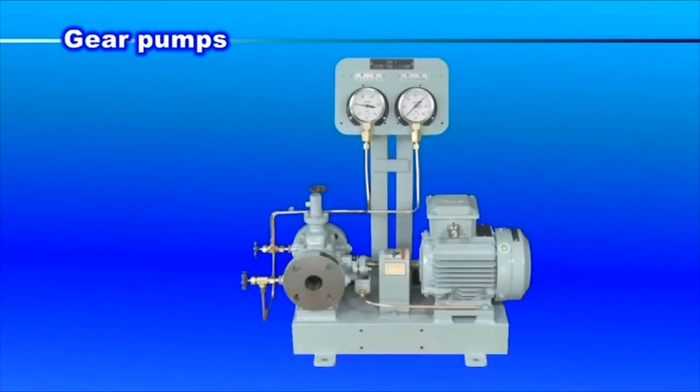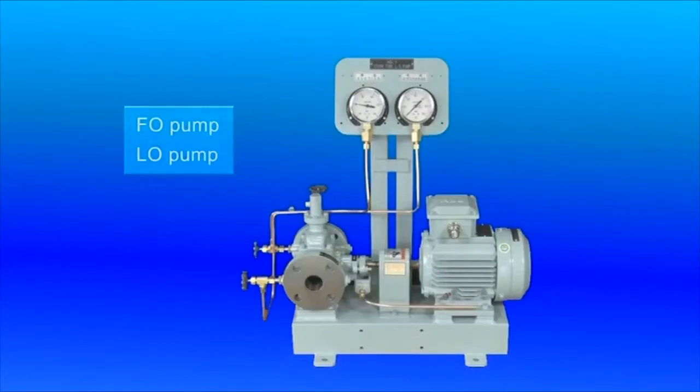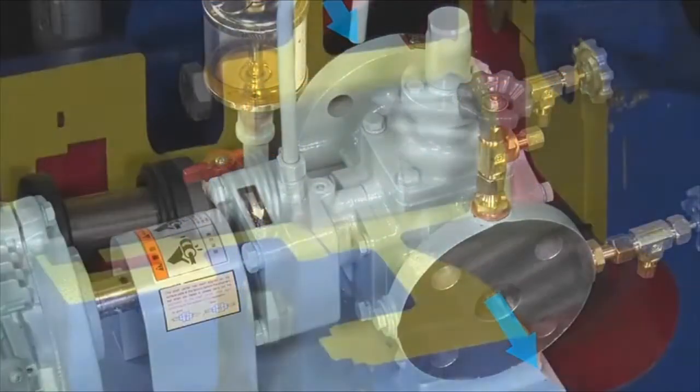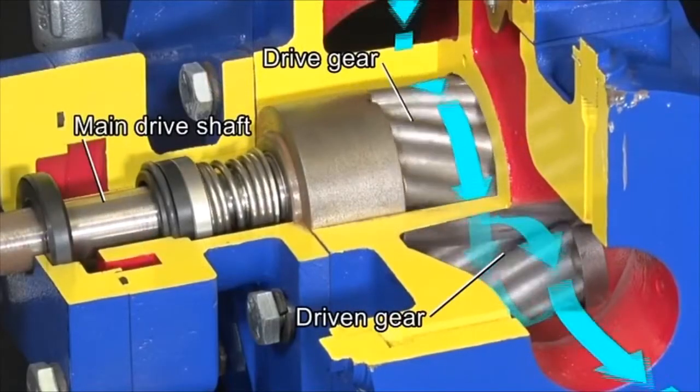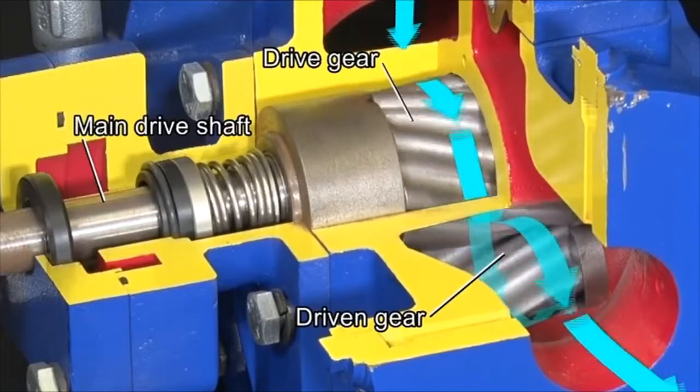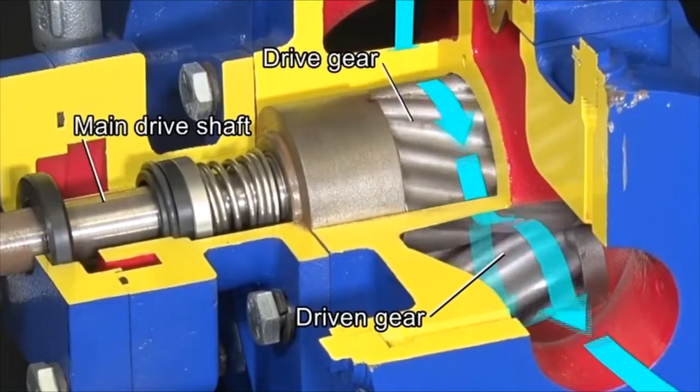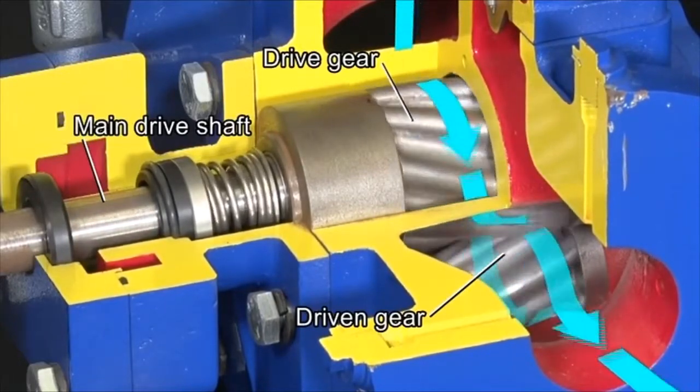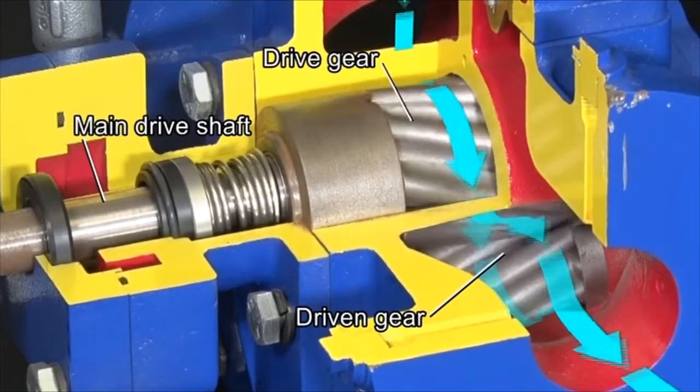Gear pumps are mainly used as fuel oil and lubricating oil pumps. Rotation of the main drive shaft moves a space created between the drive and driven gears, thereby allowing a highly viscous liquid to be carried from the pump inlet to the outlet.